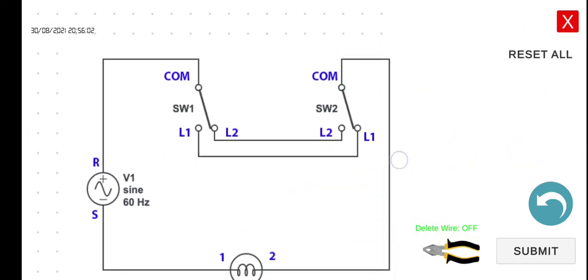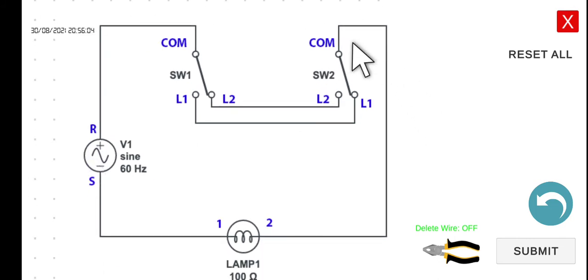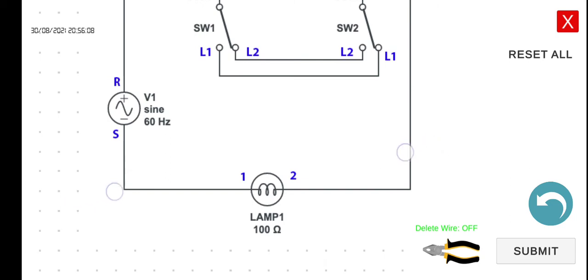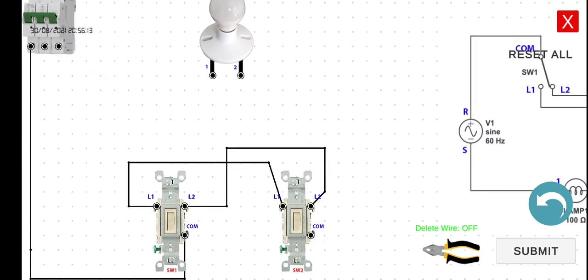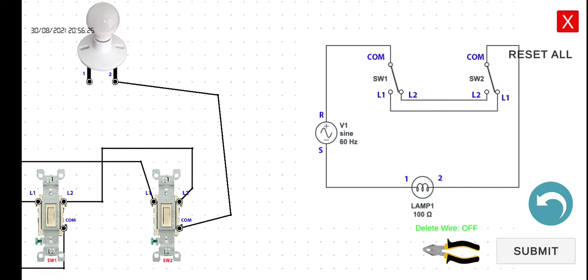We are going to connect the common of switch two to the second terminal of lamp one. The common of switch two to the second terminal of lamp one. And then we are going to connect the first terminal of lamp one to the S terminal of the circuit breaker.